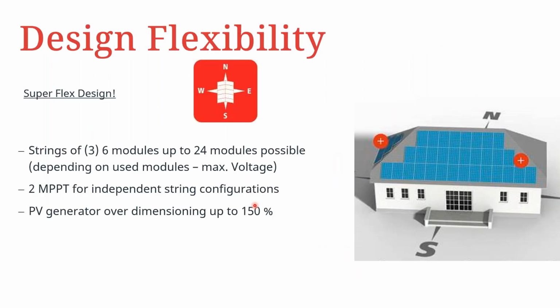We mentioned the Superflex design before, and the Superflex design for the Symo inverters would allow you to connect, let's say, up to 3 strings per MPPT, and each string would have starting from 6 modules to a maximum of 24 modules. But of course, this also depends on the used modules, what is the maximum voltage of the module, as well as the amp currents. So the PV generator over dimensioning can be done to a maximum of 150% for the Snap inverter Symo, and this is what we refer to as the DC to AC ratio.